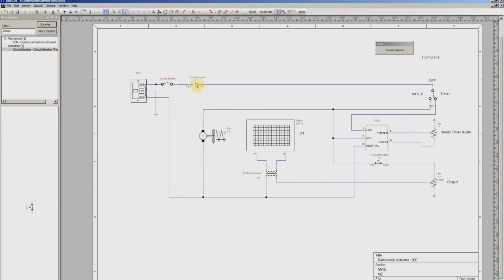And if this circuit breaker is popping, it pretty much means that you have an arc fault somewhere in the wiring insulation or inside of a switch, or the fan has gone bad electrically, or maybe, kind of as a long shot, the time delay module has gone bad internally and is causing it to pull a great deal of power between the line and neutral. But that would only happen if you switched it in the timer mode and it immediately tripped the circuit breaker. But if you switched it in the manual mode, it ran perfectly normally, that would help you nail it down to the timer module.